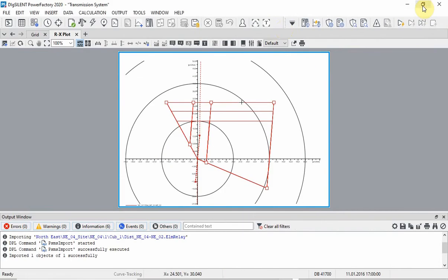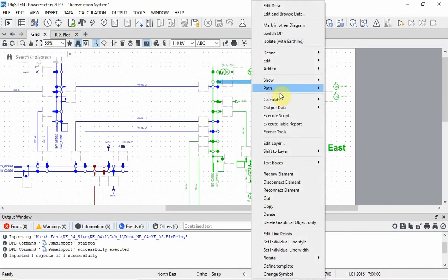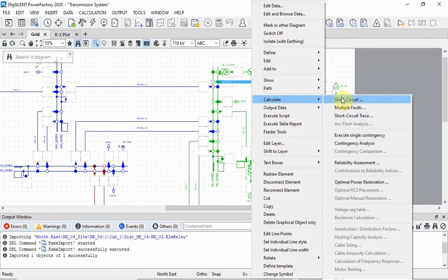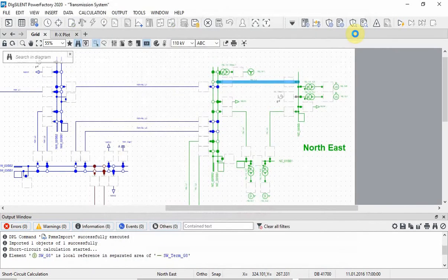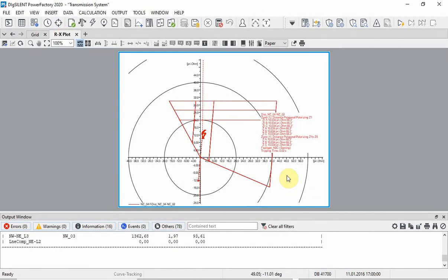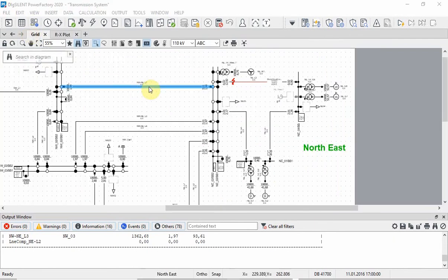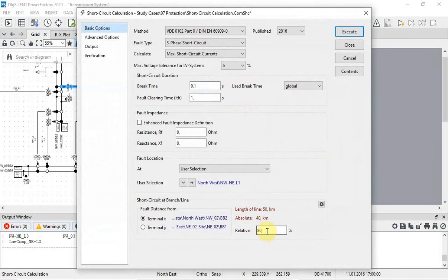Now we will check these settings in PowerFactory. A short circuit event at a point 80% along the line is analysed. This causes the relay to trip in the first zone. The same calculation is also done on the next line, and the relay also trips in the first zone.